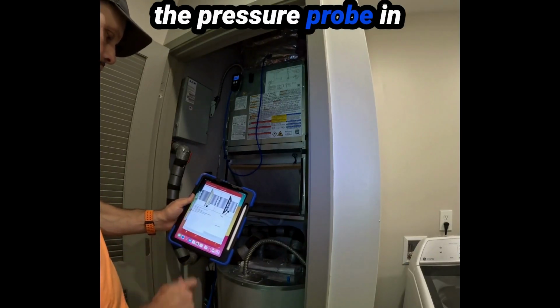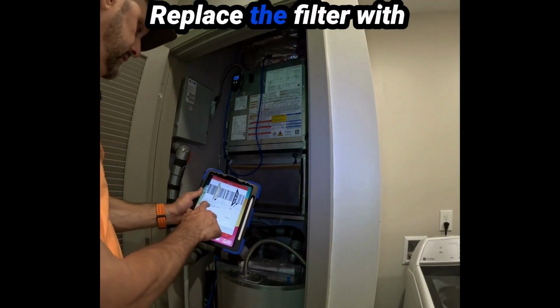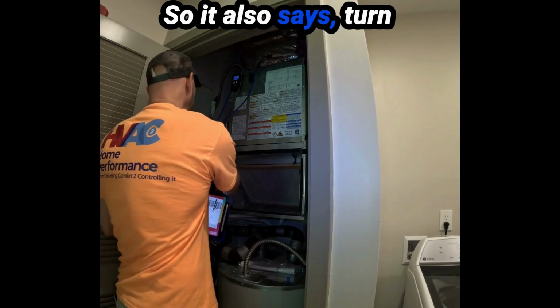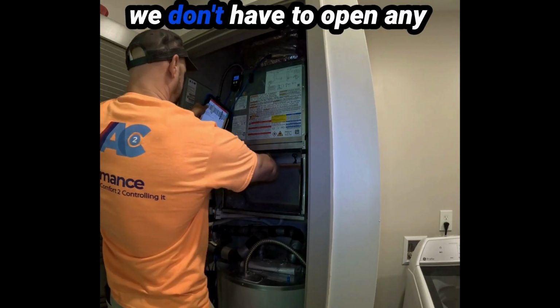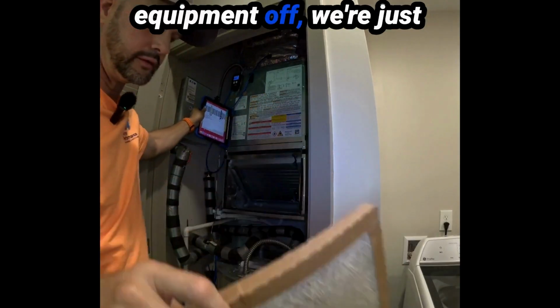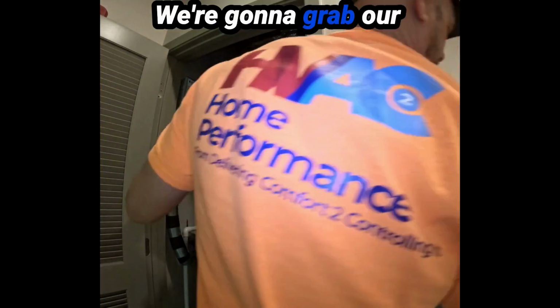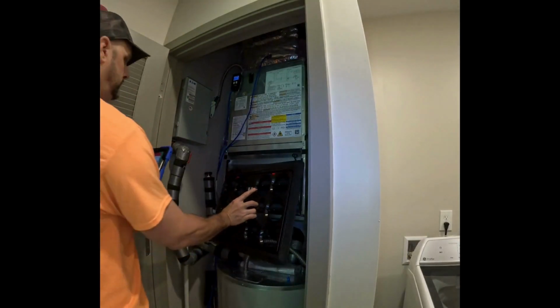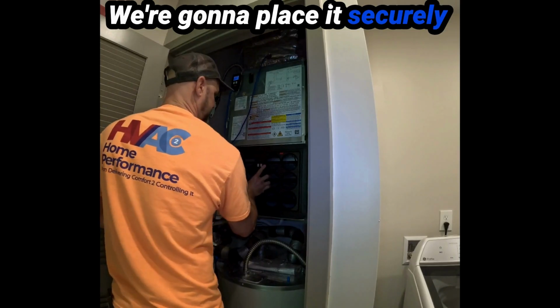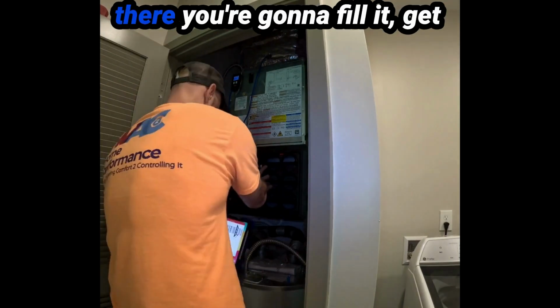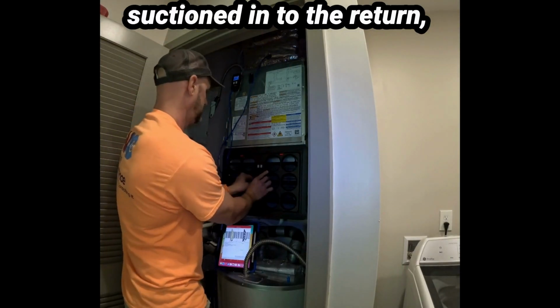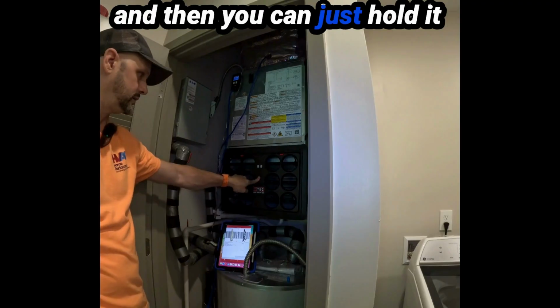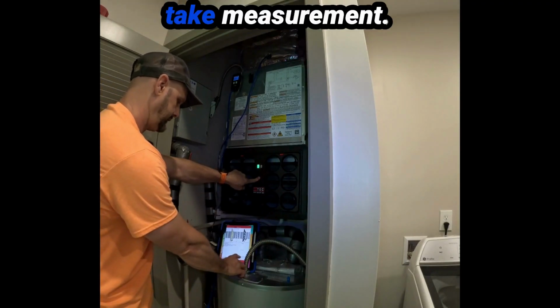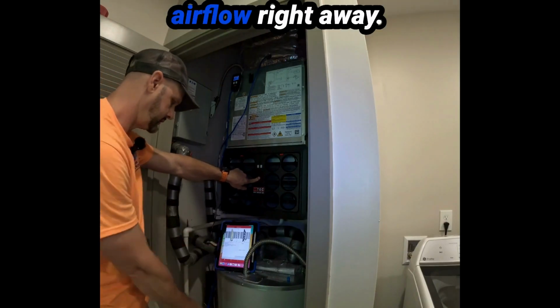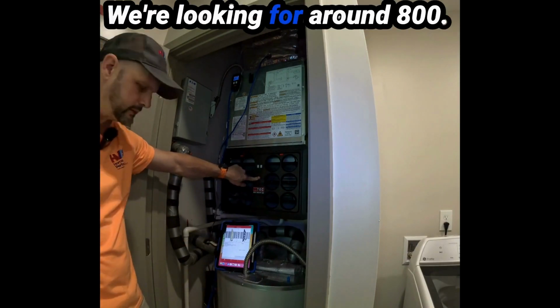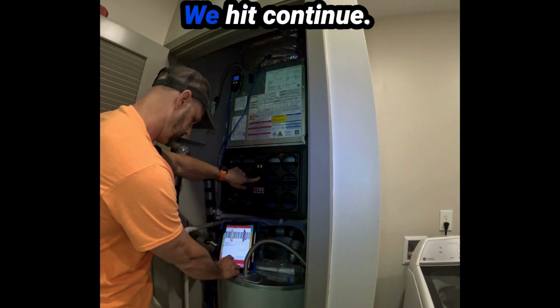Now it tells us to leave the pressure probe in the supply plenum and replace the filter with the TrueFlow device. It also says turn the equipment off, but for this one, because we don't have to open any cabinet or anything, we don't really need to turn the equipment off. We're just going to take the filter out. We're going to grab our 14x20 TrueFlow grid and place it securely. You're going to feel it get suctioned into the return, and then you can just hold it right there with your finger. We're going to hit take measurement. It gives us our total airflow right away: 733 CFM. We're looking for around 800. That's pretty reasonable. We hit continue.